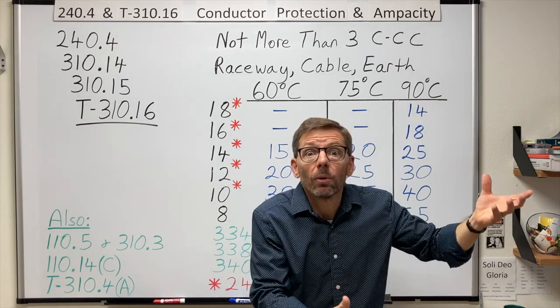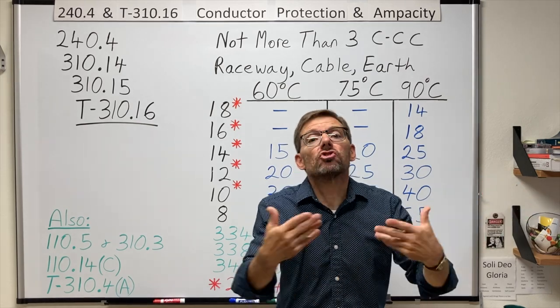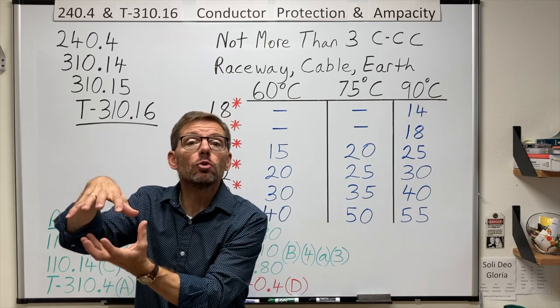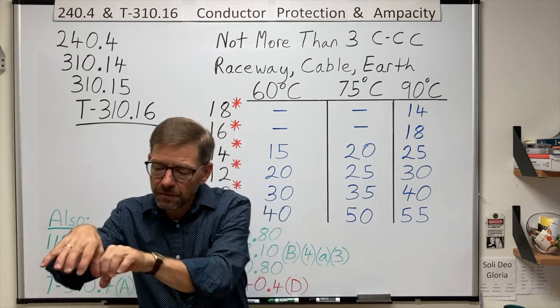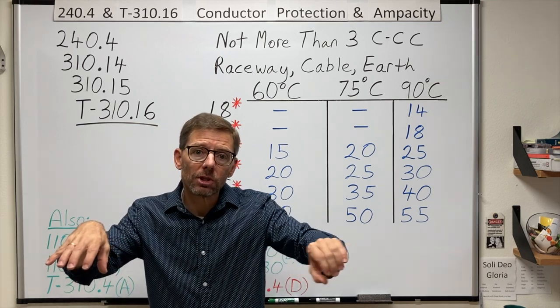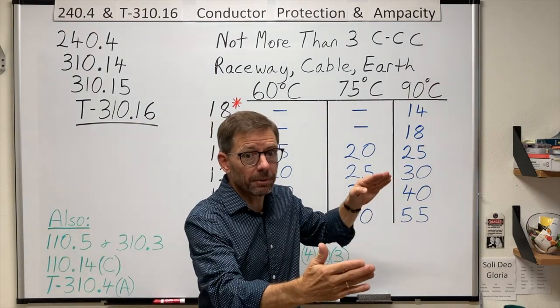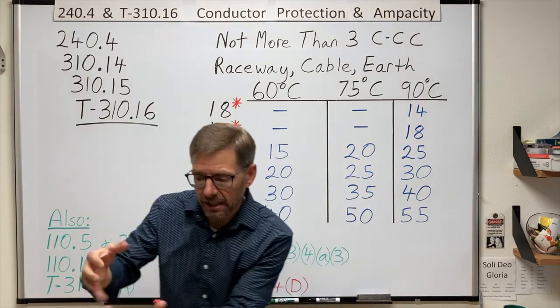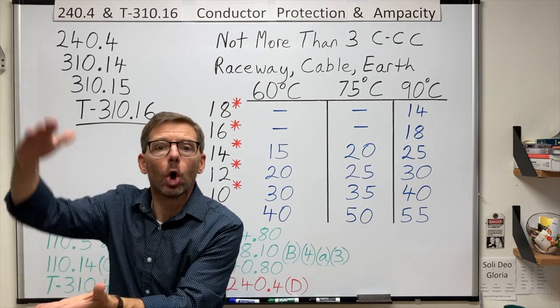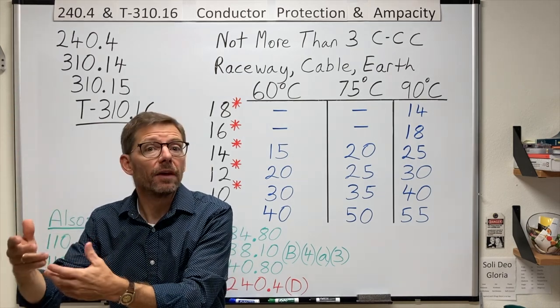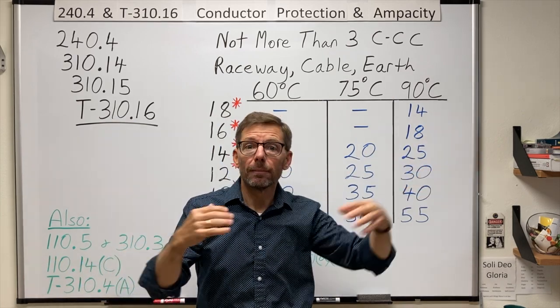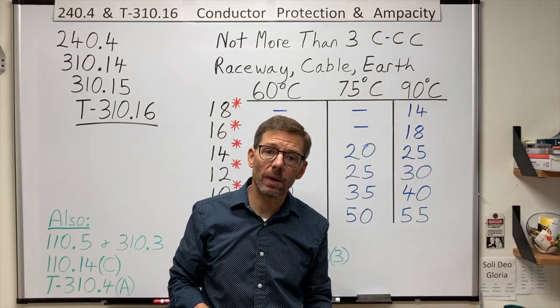And so how would I protect that conductor? Well, generally speaking, we have an overcurrent protective device, a fuse or a circuit breaker, that feeds a conductor. And if that conductor draws too much current for too long a period of time, based on the characteristics of the overcurrent device, the device will open, stopping the current flow and thereby protecting the conductor and anything down line from that overcurrent situation.